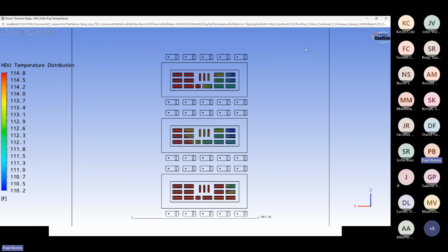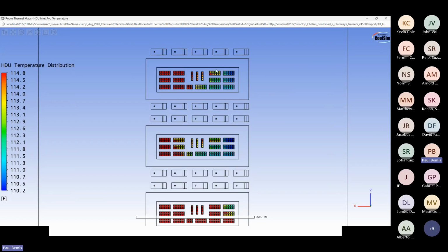The wind is actually now coming from this direction down. You can tell by the coloring. But you see that we're getting some infiltration into those chillers. I was showing you that earlier up here on the first set. Notice it's less on the second set. Kind of an interesting outcome. I wouldn't have predicted that necessarily.